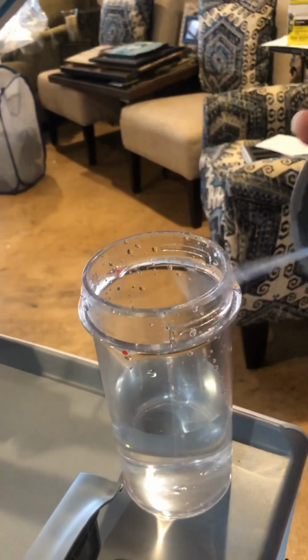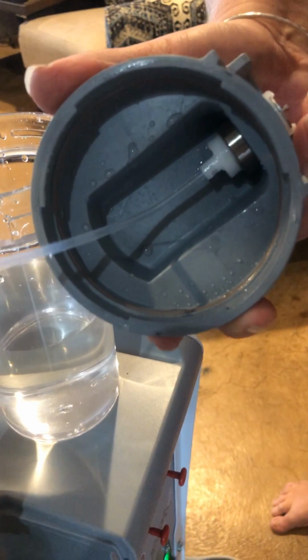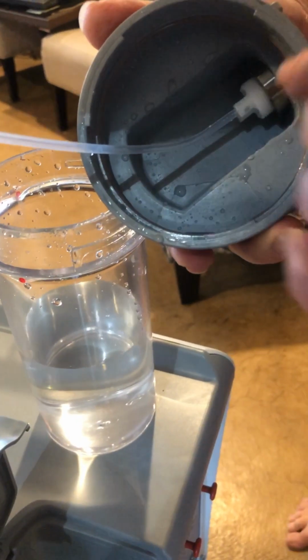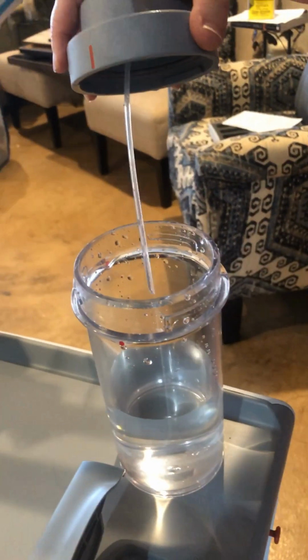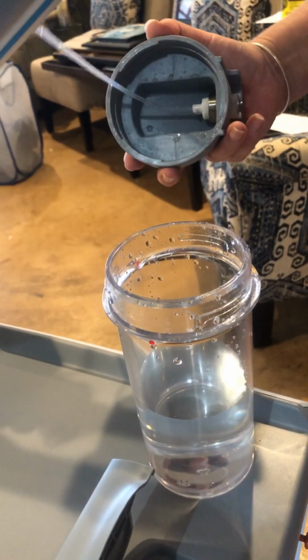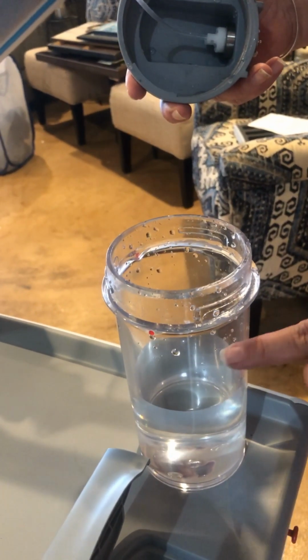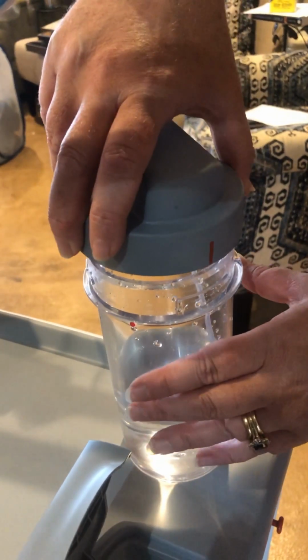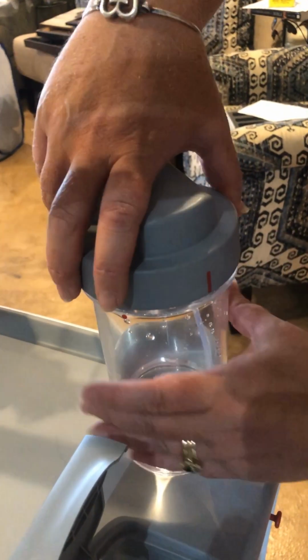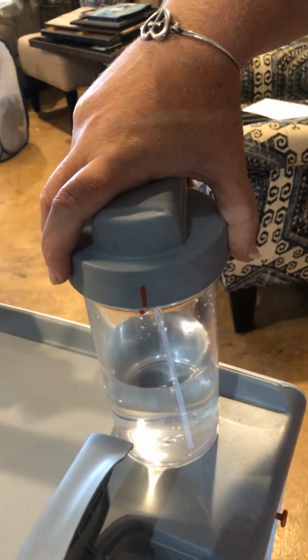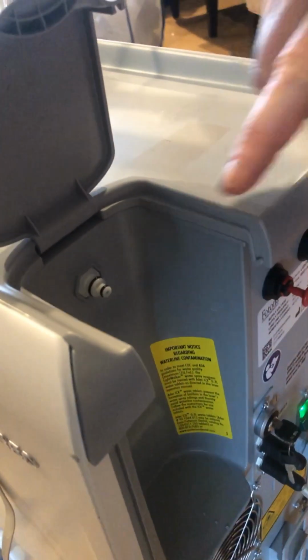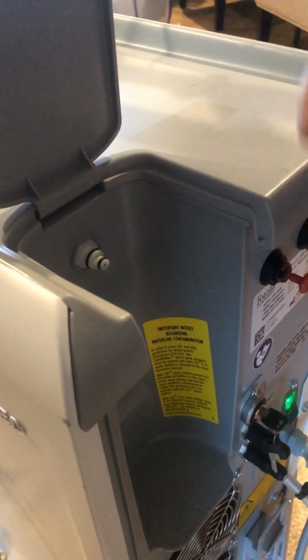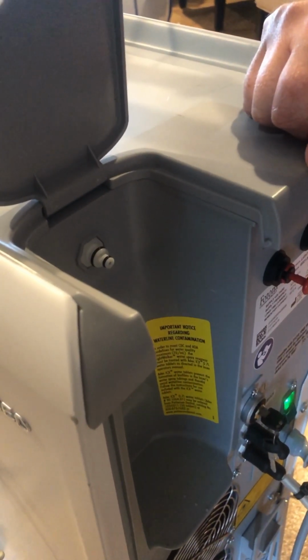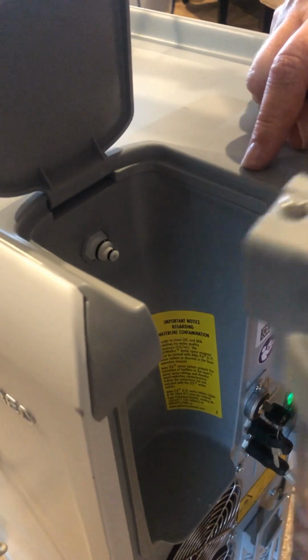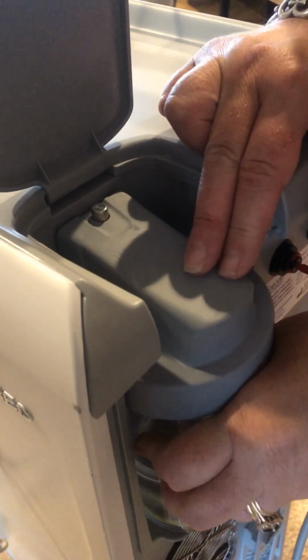There is an O-ring in here that needs to stay moistened. If it ever doesn't compress properly, re-moisten that with either a very light amount of Vaseline or lip balm, which is fine. You want to fill the water up and leave a little bit of an air gap, and then when you go to put this back in, you can line that line up anywhere between any of the dots and then turn towards one of the dots. And now we're good to go. The other area, if you're having trouble getting the air to fully compress with the water, is these O-rings, which might have gotten dry. You might need to put a very light amount of Vaseline or lip balm on that, and then you just push that straight into the connection.